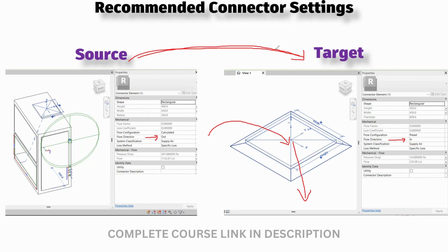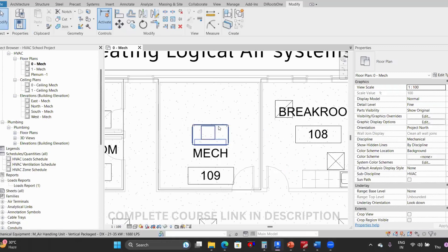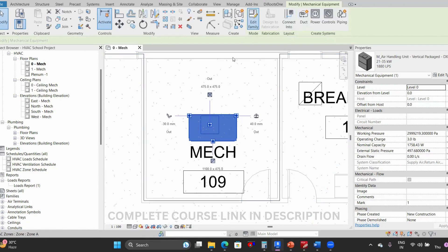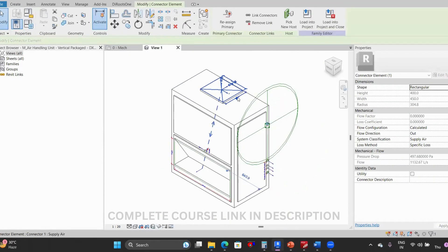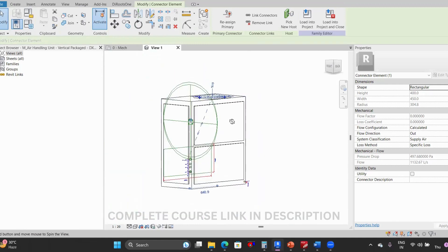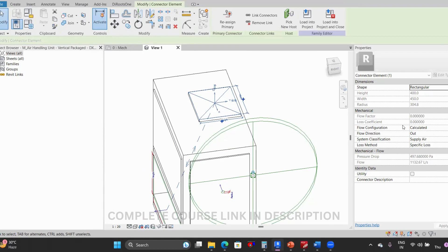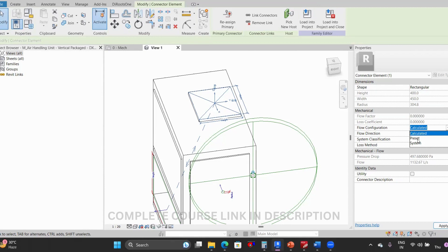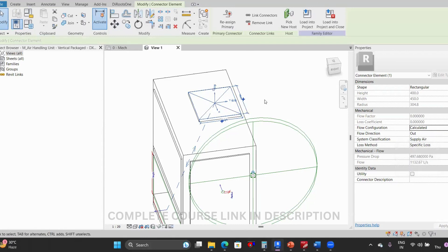Let's see the connector settings in Revit one by one. When you select the connector — on which your ductwork takeoff will connect — there are some settings. The main thing under mechanical flow is the flow configuration, which is set to 'calculated' for mechanical equipment. We use 'preset' for targets (air terminals) because we are manually feeding that information, but for mechanical equipment it is set to 'calculated' because the flow is computed once it is connected.